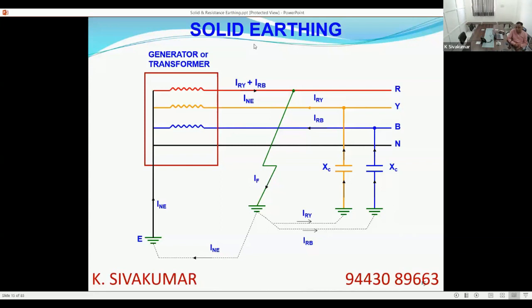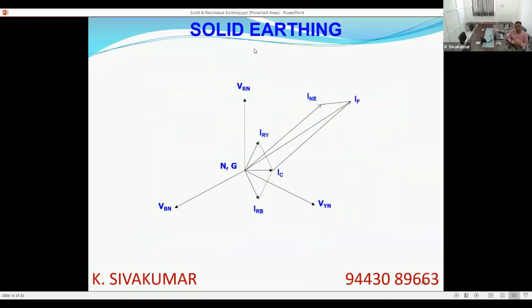Similarly, since there is a low impedance path between the earth and the neutral, current will definitely try to flow, fault current will try to flow back to the neutral from the faulted zone. If you draw a vector diagram, you can see IRY is the Y phase capacitive current, IRB is the blue phase capacitive current feeding into the fault. The neutral and ground are solidly connected. Since R phase is grounded, there is no RN voltage. Now the capacitive current itself is the vector sum of IRY and IRB, which has become IC.